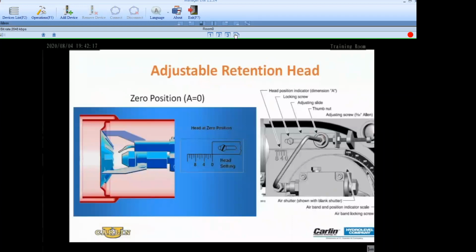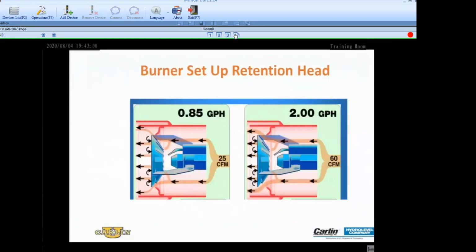Flame retention, a concept often misunderstood by technicians. Here's something that you cannot see. No matter how many times you look inside that peephole into the combustion chamber, you can't really see whether you've got good retention on that head, on that burner. It's assumed the flame looks good, the flame has the right color, it's crisp, it's sharp, the tips are nice, it's not too orangey, it's not too white. These are all the things that technicians are looking for. But do you have good flame retention? There's only one way to know. You've got to take a combustion test. You've got to understand what your numbers are telling you.